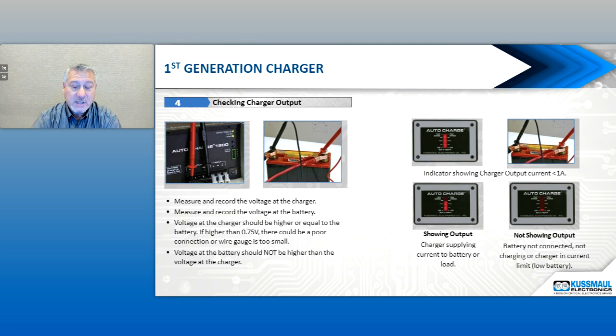But if the voltage at the charger is more than 0.75 volts higher, it's more than likely you have a bad connection or the gauge wire is too small and you're losing voltage to the battery. The voltage should never be higher at the battery than at the charger.